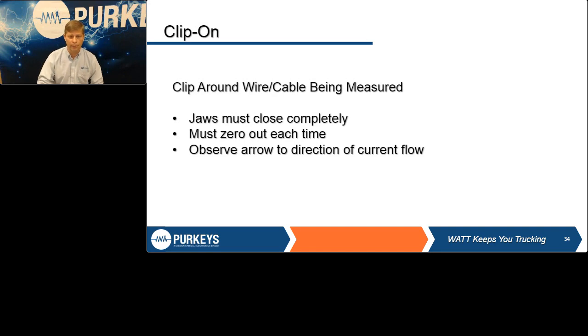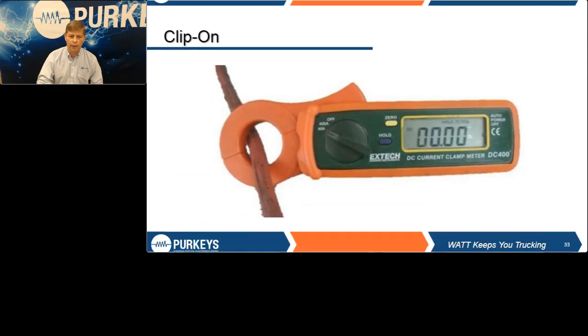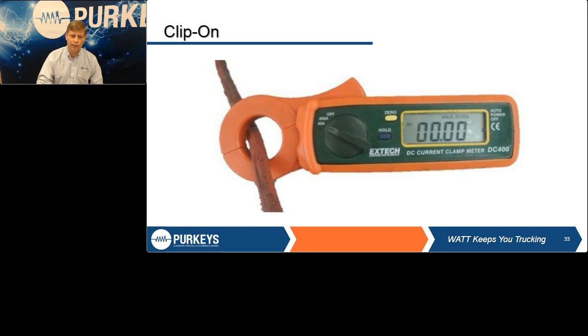Depending on the type of meter, going back a slide here again, this one has a zero button. So whenever you go to use it, hit the zero button, make sure it reads all zero. Some of the older ones used to have what we call a thumb wheel, where you had to push it in with your thumb and turn it left and right. Those were a huge pain because you'd go one direction and be at +5, go the other direction and it jumps all the way to -7, turn it back and it jumps up to +18 or whatever.